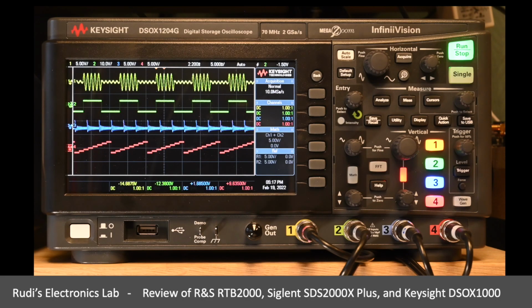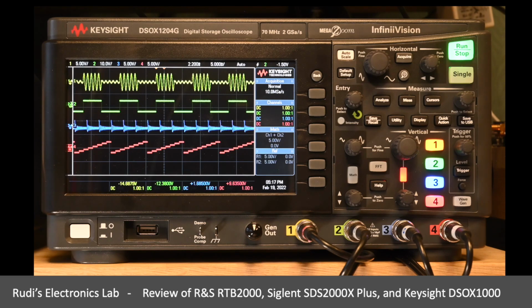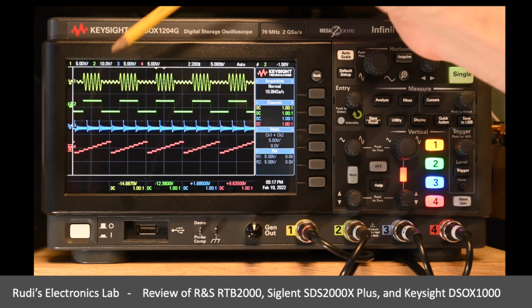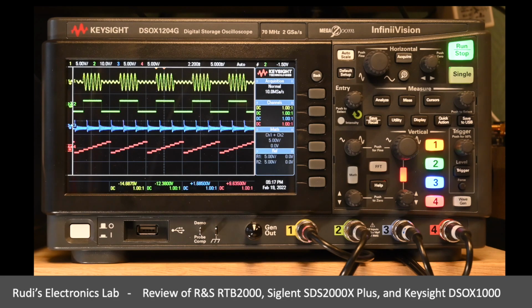Now let's also take a look at the implementation of measurement at the Keysight. And of course we know this is a rather different device, also in the way that the user interface works. Let's do it. And of course I'm showing you the same signals that go into the device right now. It has a 10 division horizontal screen, so we get to see 5 of these measurements, always using the same time base as the previous ones.